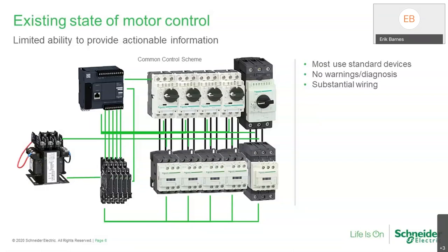And you think about the scheme of how we set this up. If I've got a logic controller in the system, I've got I/O that I need to connect to get information back from the contactor, like whether its status is open or closed. I need information back from the overload protection: is it in a tripped state or not? I usually operate the coil through an interposing relay so I don't inadvertently damage the I/O for the PLC, which is expensive to replace. So this is the network we have set up, a lot of wires running around.